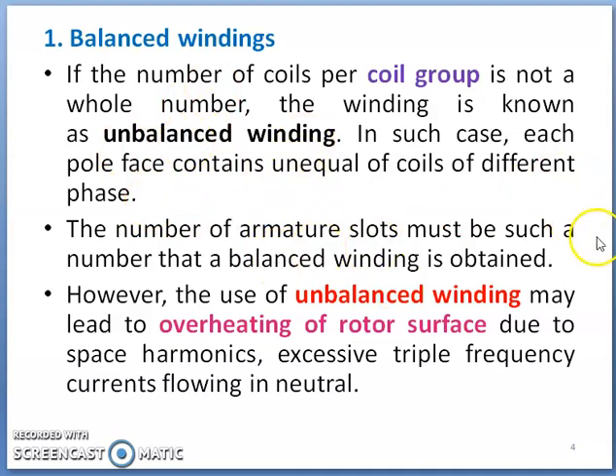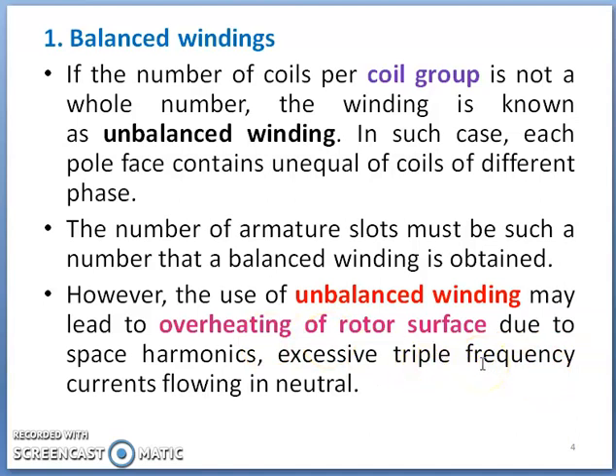The number of armature slots must be such that a balanced winding is obtained. When the number of slots are designed for a given diameter of machine and output rating, the winding should be a balanced one. The adverse effects of unbalanced winding include overheating of the rotor surface due to space harmonics, and excessive triple-frequency currents — three times the supply frequency — flowing in the neutral.